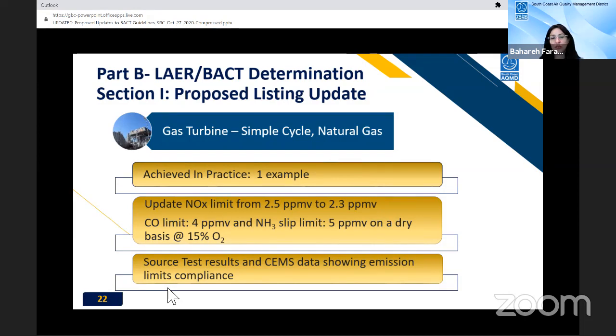The facility, they were very cooperative to provide us with all those source test data and mostly the continuous emission monitoring data for 1 year for 2 of their units. So we are proposing to reduce current NOx limit from 2.5 to 2.3 ppm for the simple cycle natural gas turbine, and the CO limit will be 4 ppm, going down from 6 to 4 ppm. But the ammonia slip limit would be still 5 ppm.